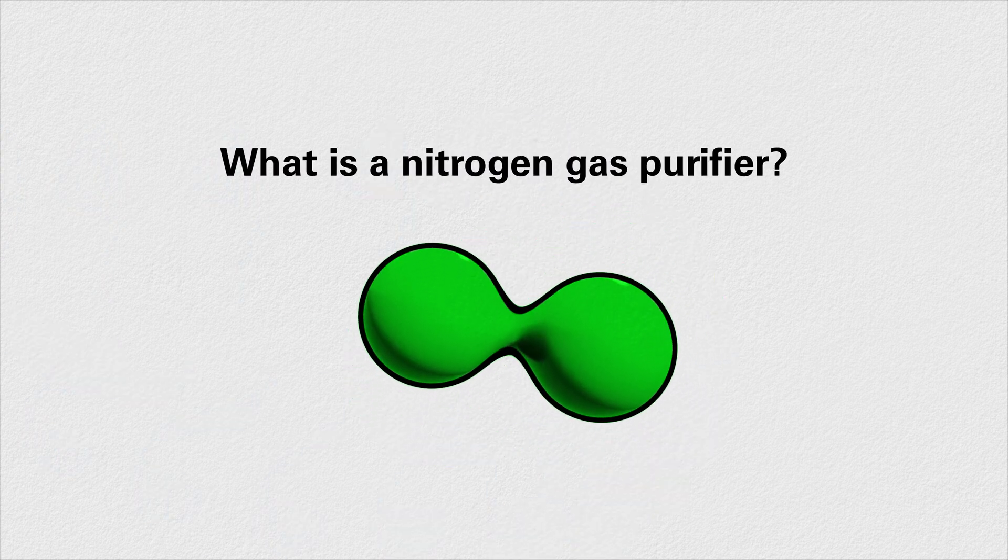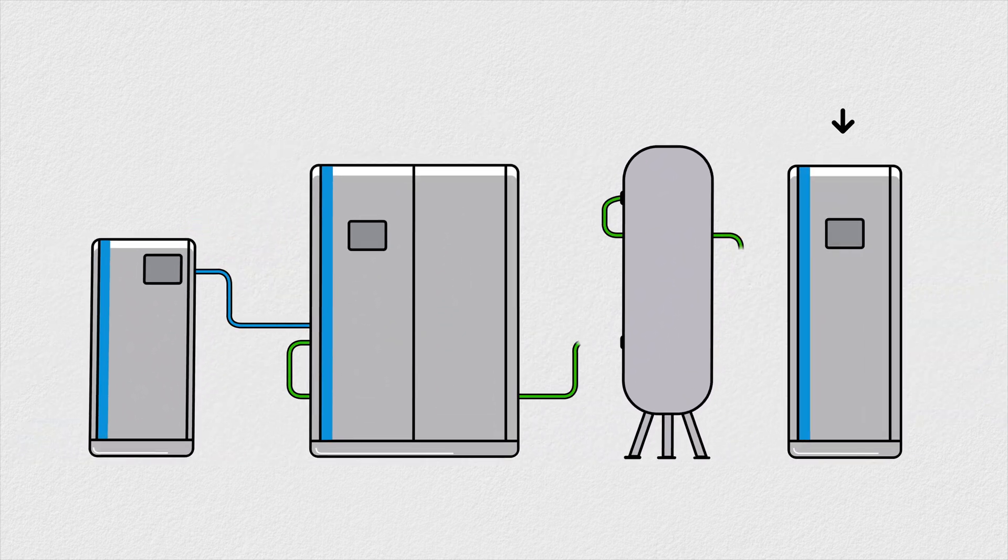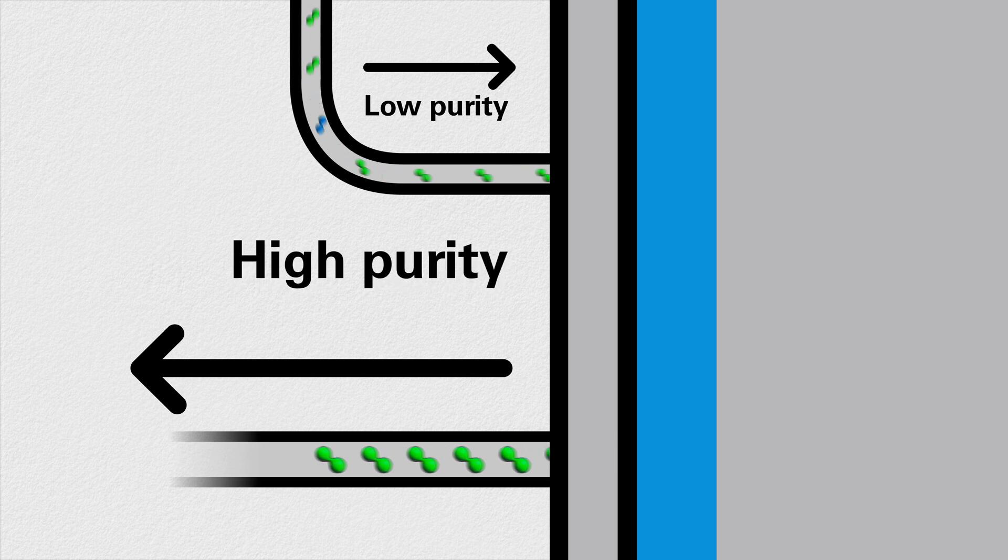What is a nitrogen gas purifier? A nitrogen gas purifier is a machine that operates as part of an on-site nitrogen generation system. It takes lower purity nitrogen produced by a nitrogen gas generator and boosts it to a purity of 99.999% or more.